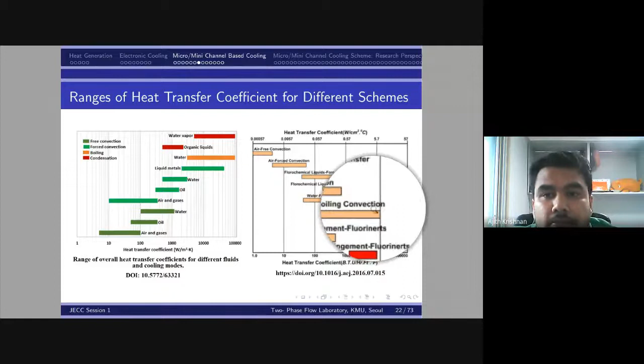Next, here are different methods of cooling and their heat transfer coefficient ranges: water, boiling, convection. The range is very high for water, from 1,000 to 10,000 units, while for air convection it's nearly in the order of 10 to 100. See how ineffective air cooling is compared to how effective water-based boiling, two-phase flow cooling is. That's the peculiarity of different cooling methods.